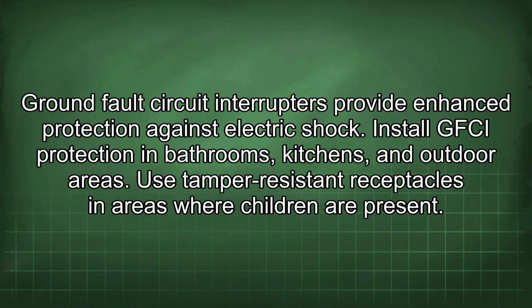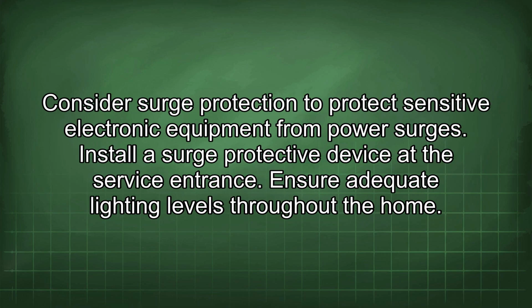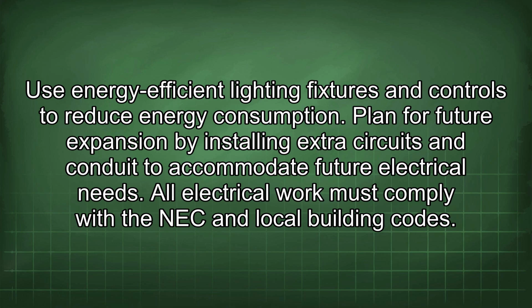Use tamper-resistant receptacles in areas where children are present. Consider surge protection to protect sensitive electronic equipment from power surges. Install a surge protective device at the service entrance. Ensure adequate lighting levels throughout the home. Use energy-efficient lighting fixtures and controls to reduce energy consumption. Plan for future expansion by installing extra circuits and conduit to accommodate future electrical needs.